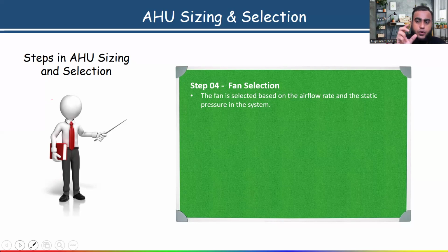If you have a little bit of idea about HVAC, for any fan, either the fan inside the AHU or an exhaust fan, we always have to calculate the external static pressure. As an HVAC designer, it is our responsibility to calculate the external static pressure, because we have to submit this detail to the manufacturer. The internal static pressure value will be given by the manufacturer. Our main target is to calculate the external static pressure.